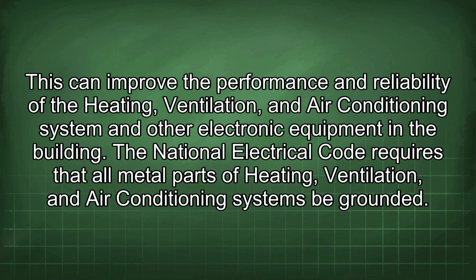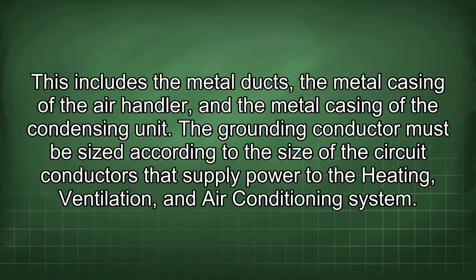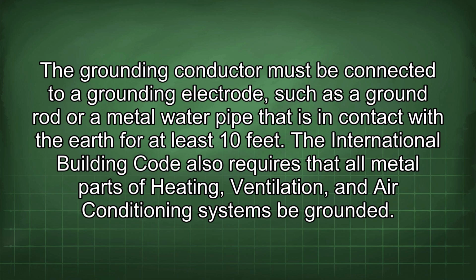in the building. The National Electrical Code requires that all metal parts of heating, ventilation, and air conditioning systems be grounded. This includes the metal ducts, the metal casing of the air handler, and the metal casing of the condensing unit. The grounding conductor must be sized according to the size of the circuit conductors that supply power to the heating, ventilation, and air conditioning system. The grounding conductor must be connected to a grounding electrode, such as a ground rod or a metal water pipe that is in contact with the earth for at least 10 feet.